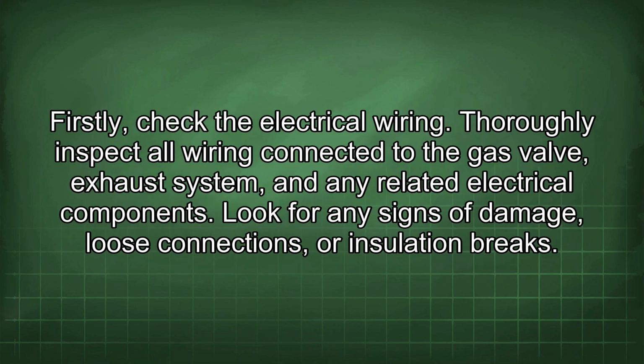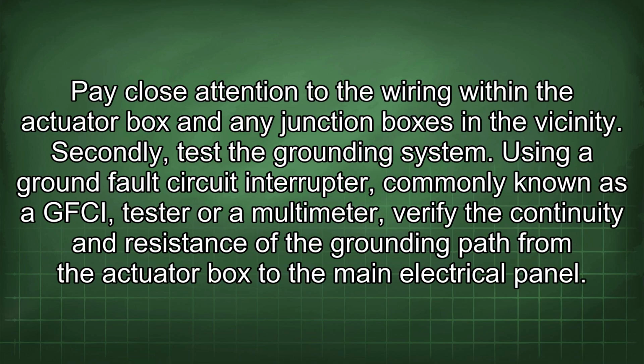Firstly, check the electrical wiring. Thoroughly inspect all wiring connected to the gas valve, exhaust system, and any related electrical components. Look for any signs of damage, loose connections, or insulation breaks. Pay close attention to the wiring within the actuator box and any junction boxes in the vicinity.